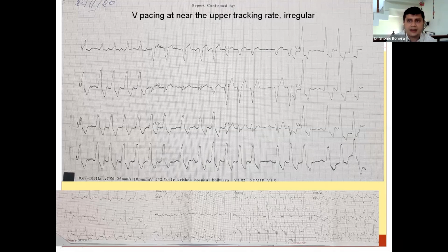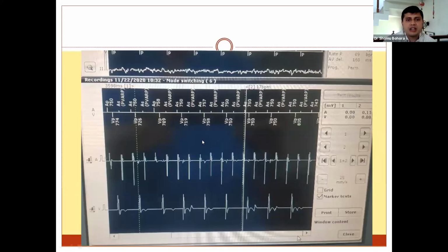Whenever you have ventricular pacing occurring at a higher rate, that is the upper tracking rate. The pacemaker ventricle should pace maximum at the upper tracking rate, which is programmed to around 120, 130. So if you have pacing at the upper tracking rate, what you have to consider, A, is a pacemaker mediated tachycardia, and second is an atrial arrhythmia, which is causing this increased rate. When we interrogate, these are the electrograms. You can see that the A waves in the upper channel are more than the V waves in the lower channel.